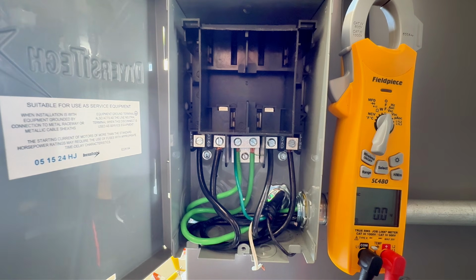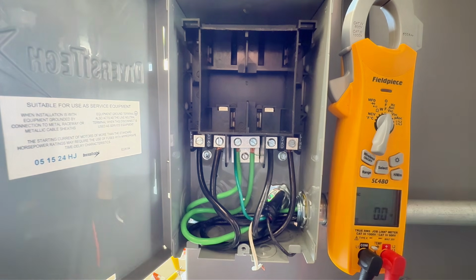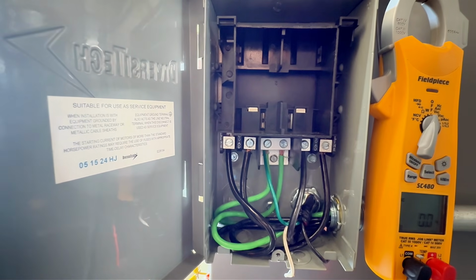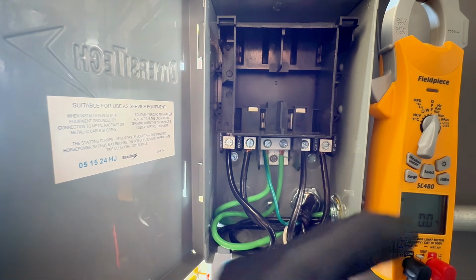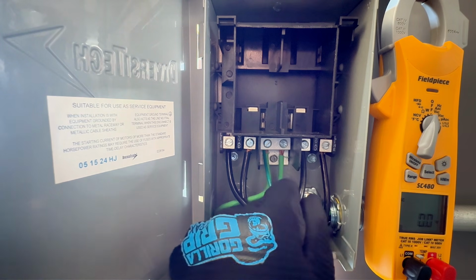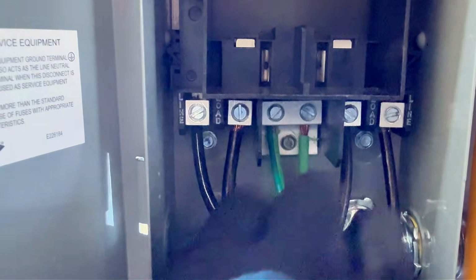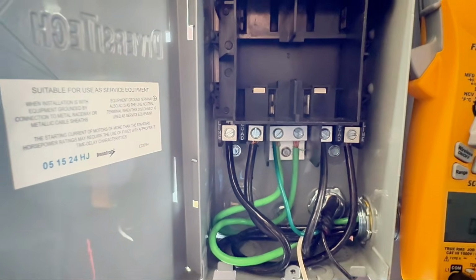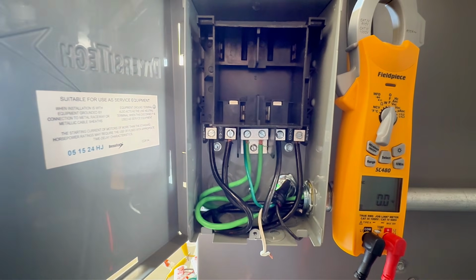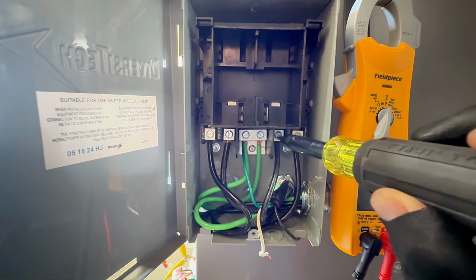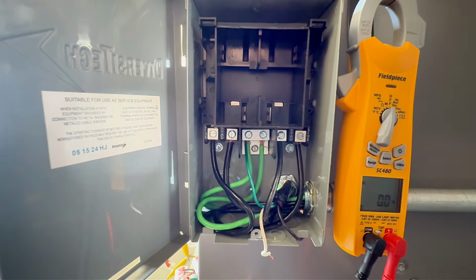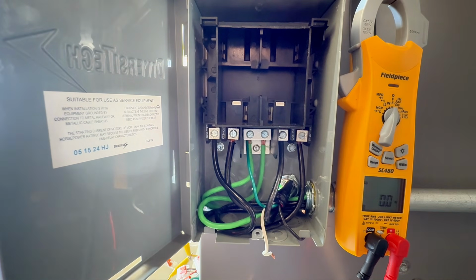Well, what could happen is these wires here are not tight enough. I'm going to show you with a thermal camera how to check if it's overheating or not. There's another little test you can do with the meter, but a thermal camera will confirm it. In this specific one, this is going to my load. I want you to see how loose that wire is. You see that? It's moving a lot. You do not want that, especially where you're going to have a lot of current going through. Now I do have to tighten this just a little bit more, or it won't make contact, because I have to turn on the compressor and show you what would happen if it's loose. And it's still loose.